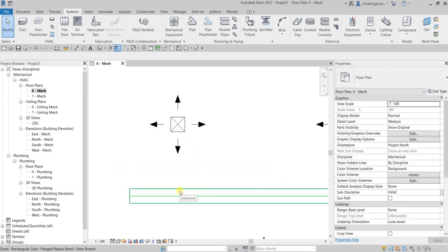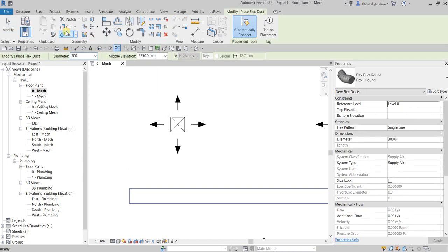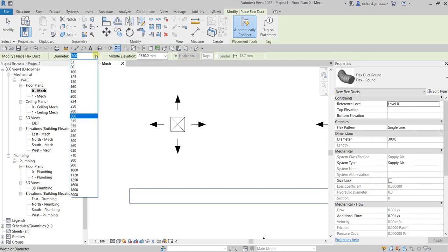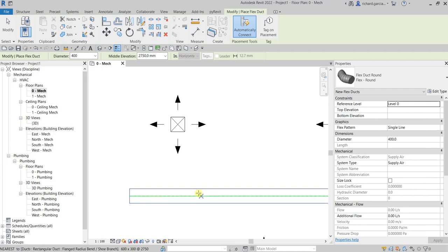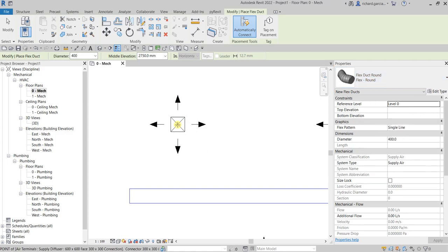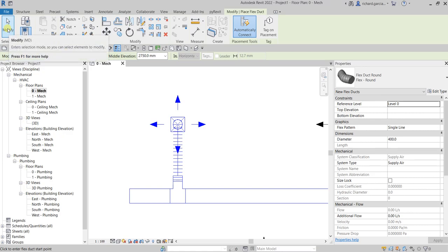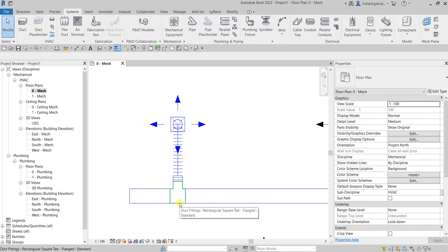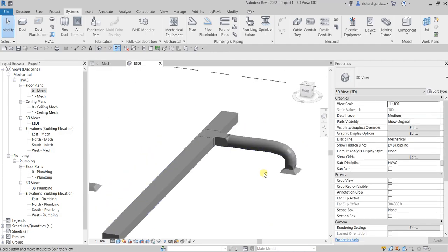Now the first thing we'll be doing is creating our flexible duct and connecting it to our duct to see what it looks like. From the Systems tab I'm going to select the flexible duct, and I'll use a diameter of 400 with a middle elevation of 2750 — the same height as my duct. I'll pick the connection point and connect it. As you can see, the default connection here is a T-fitting or T-junction type.